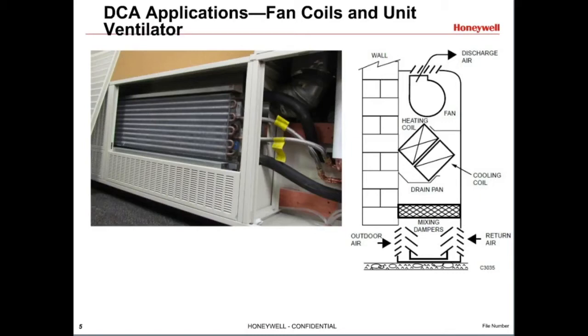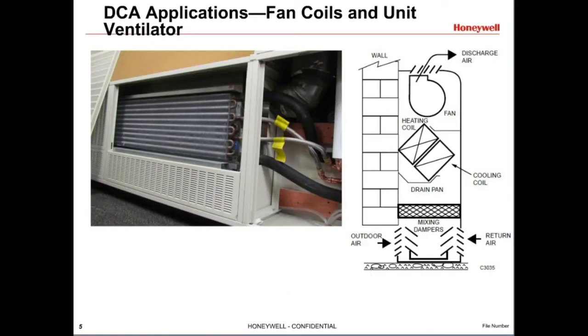The heating may be done with hot water and a coil, steam, or electrical resistance elements. The cooling may be chilled water and a coil, or mechanical refrigeration. Because of size constraints, these units require small actuators. The valves may need actuators that are fail-safe, where they return either to the open or closed position, or non-fail-safe, where they hold in the last position when power is removed. Unit ventilators need a spring return actuator for the outdoor air damper. They may have a return air outdoor air diverting damper that is controlled by either style of actuator.